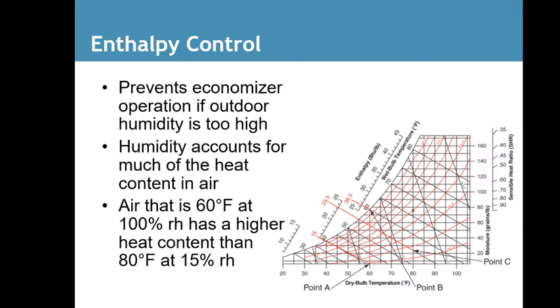For example, if you know what the relative humidity is and the temperature is, you can get a dew point, which is used to figure out charging. Or if you know the dew point, you can figure out what the relative humidity outside is. But look into that in your book. Again, I don't think there's going to be any questions for you on this, but it's a good thing to see, because some units that you will install will have a psychrometric chart to tell you how to charge this unit using either subcool or superheat and where that should fall.